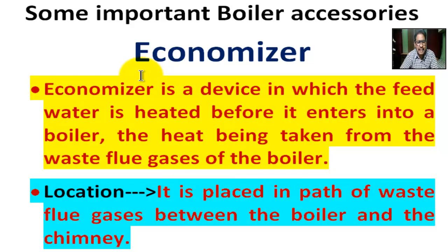Actually, an economizer is a device used to heat feed water by utilizing the heat in the exhaust flue gases before leaving to the chimney. Okay. The economizer improves the economy, that means saves money, of the steam boiler. Okay.